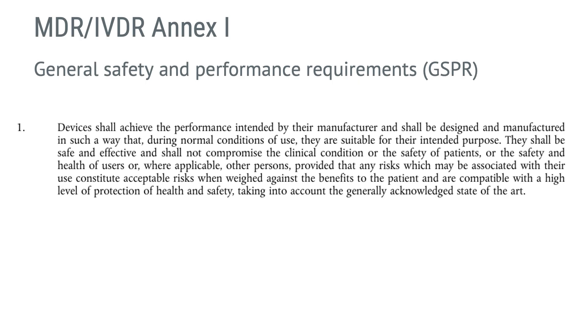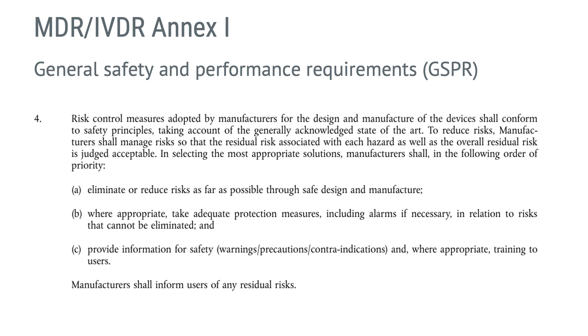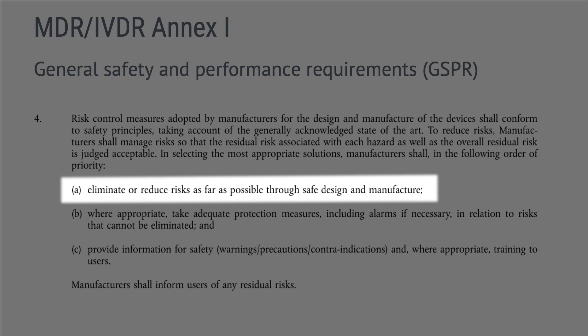The GSPR first requirement states that devices shall achieve the performance intended by the manufacturer and shall be designed and manufactured in such a way that, during normal conditions of use, they are suitable for the intended purpose. Manufacturing is mentioned in the very first requirement, as it is an important factor in ensuring the safety of the device. GSPR point 4 discusses risk control measures and includes the requirement that manufacturers shall eliminate or reduce risks as far as possible through safe design and manufacture. Process validation is one way, and sometimes even the only way, to ensure that risk control measures are effective.